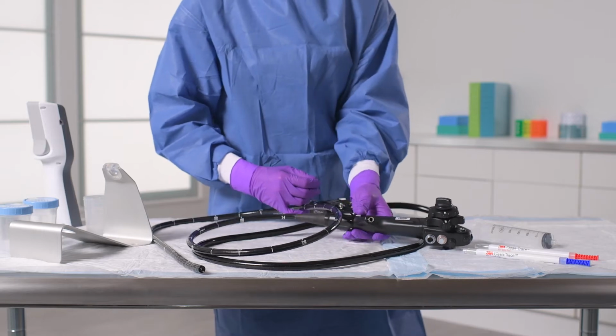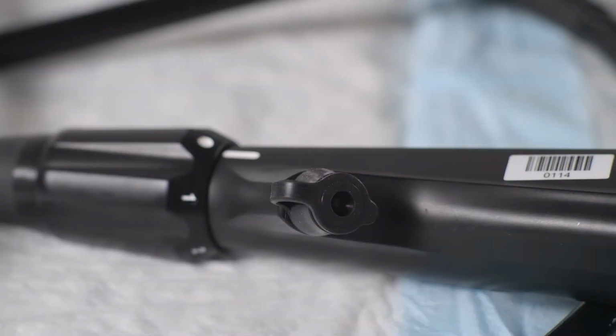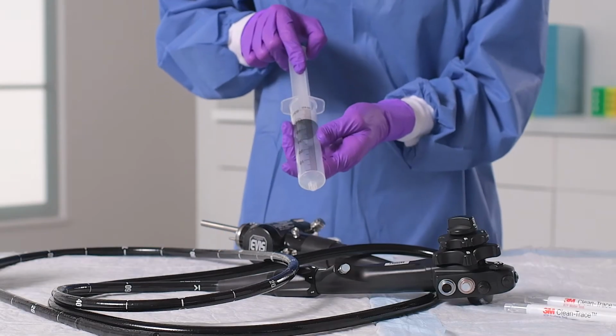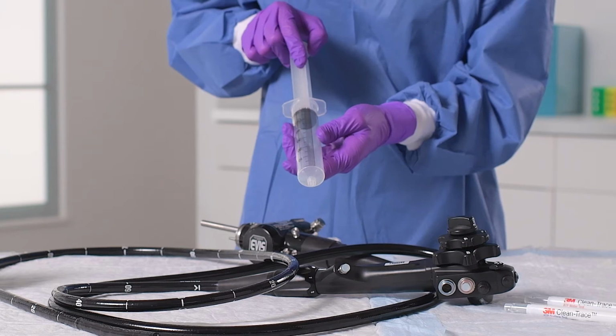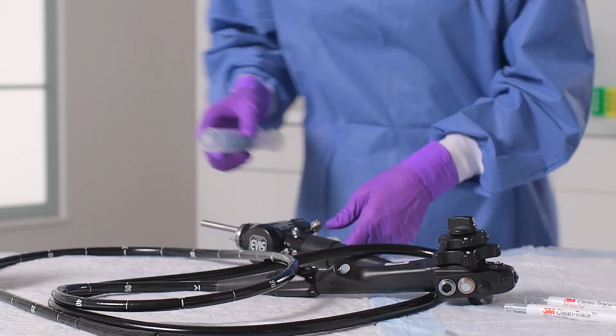For the instrument port on Olympus brand endoscopes, you can use a second plug. For other endoscope brands, make sure the instrument port is covered with the instrument port cover. Note that the connectors and plugs are for single use only, so be sure to discard them when you have completed your test. Next, fill a sterile 60 cc syringe with air, then attach the syringe to the connector.